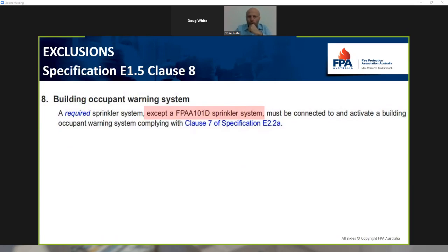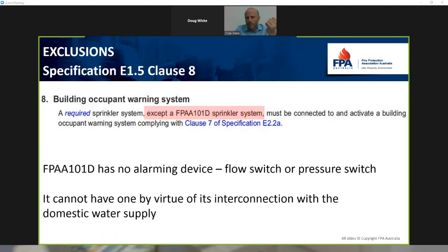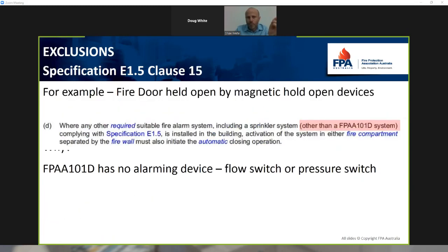Where a building occupant warning system is required, you can't use a 101D system. One of the things about the 101D system is it does not generate alarms. It has no flow switch or pressure switch. For the same reason, you can't have alarm generating equipment, open doors or shut doors, or have other functionality. If you needed that functionality for your building application, you can't use a 101D system because it doesn't have those pressure sensing and flow sensing devices.